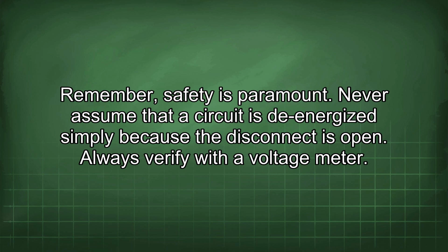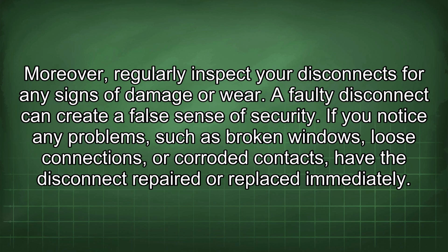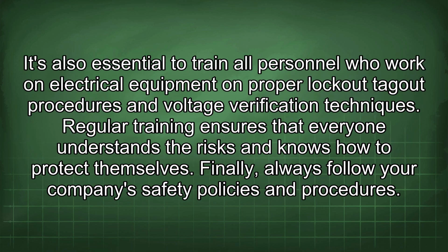Always verify with a voltage meter. Moreover, regularly inspect your disconnects for any signs of damage or wear. A faulty disconnect can create a false sense of security. If you notice any problems, such as broken windows, loose connections, or corroded contacts, have the disconnect repaired or replaced immediately. It's also essential to train all personnel who work on electrical equipment on proper lockout-tagout procedures and voltage verification techniques. Regular training ensures that everyone understands the risks and knows how to protect themselves.